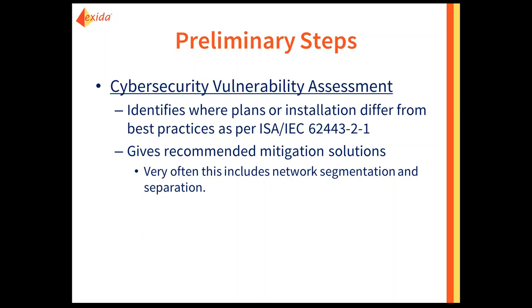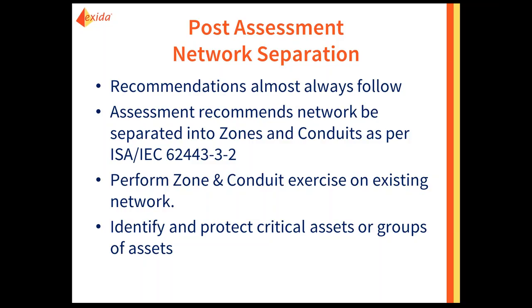Once you finish the actual assessment, the mitigation recommendations almost always require some sort of network segmentation or separation. We still find very flat or unsegmented networks within industrial control systems. Steps include performing zoning and conduit exercises to identify common areas of security or functionality and protect the most critical assets — because many industrial control system devices are still fragile and their Ethernet ports cannot handle normal network traffic.